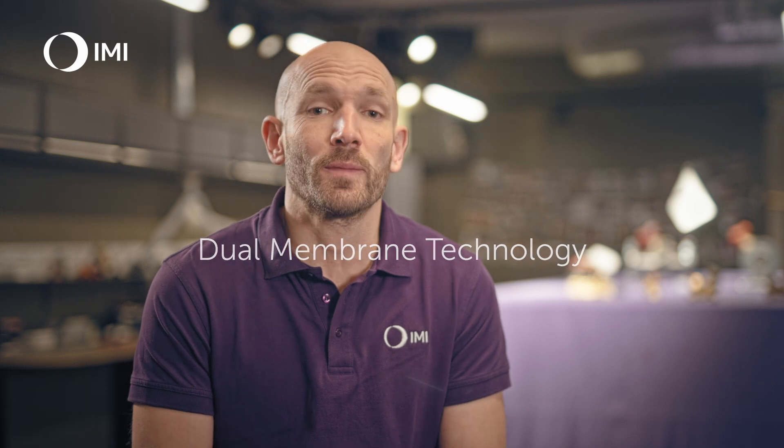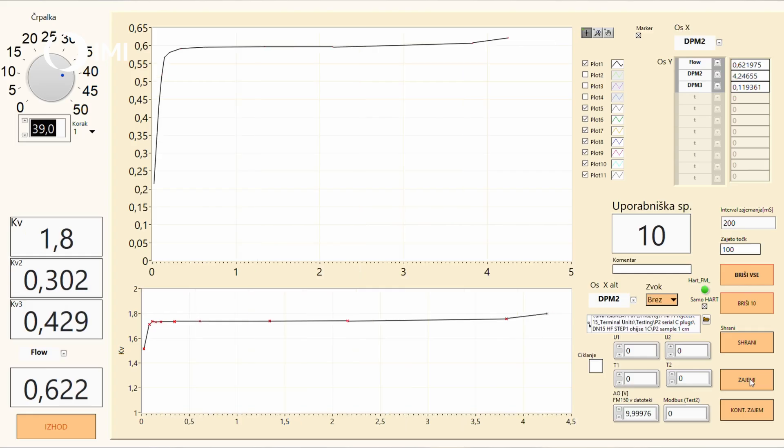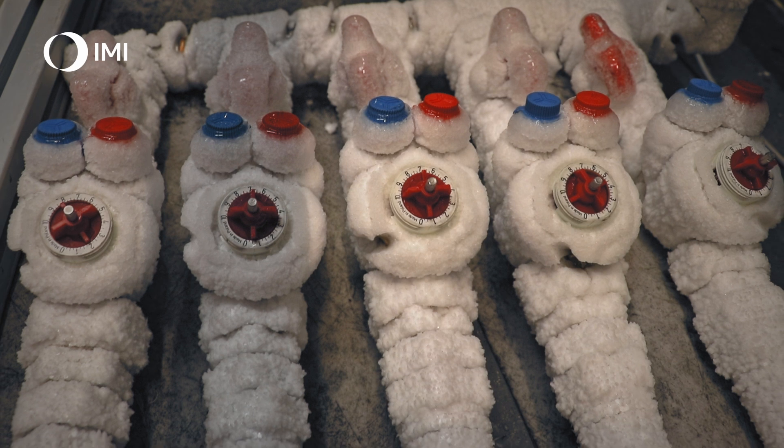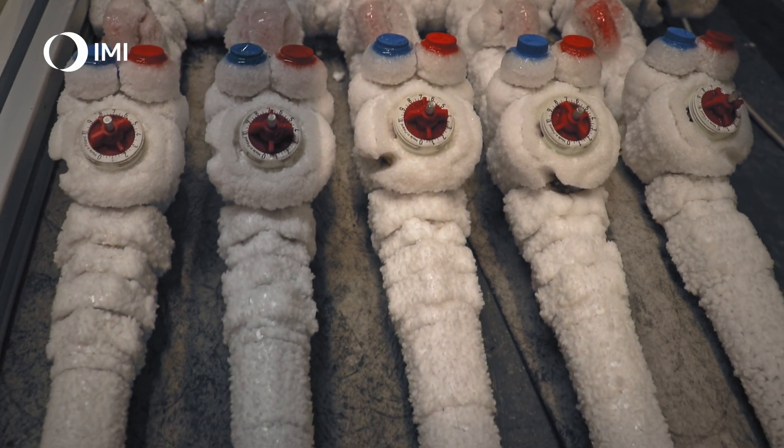The TA Nano helps the HVAC system achieve greater energy efficiency, mainly due to its dual membrane technology. This technology delivers very low hysteresis of the P-band, a low Δp min, excellent flow control, and superior resistance to higher system differential pressure — meaning that the TA Nano can withstand even the harshest system conditions while ensuring high energy efficiency.